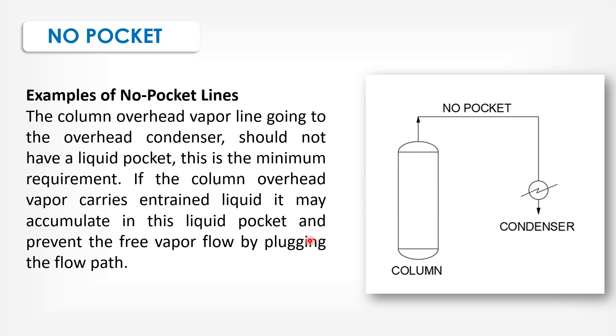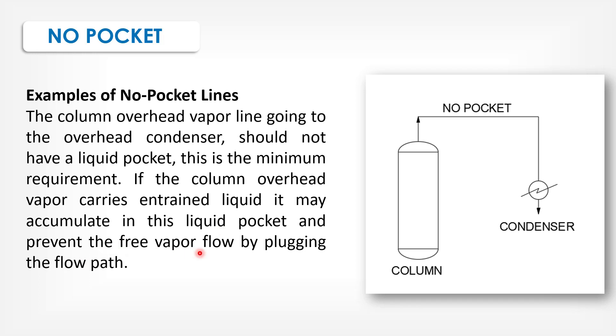Example of no pocket lines: The column overhead vapor lines going to the overhead condenser should not have a liquid pocket. This is the minimum requirement. If the column overhead vapor carries entrained liquid, it may accumulate in this liquid pocket and prevent the free vapor flow by plugging the flow path.